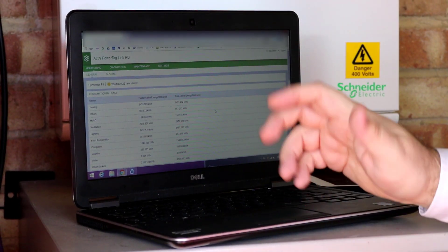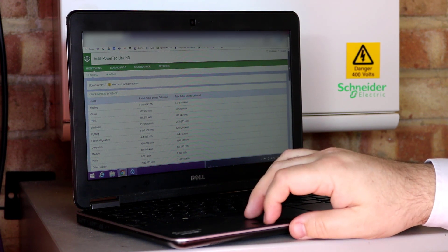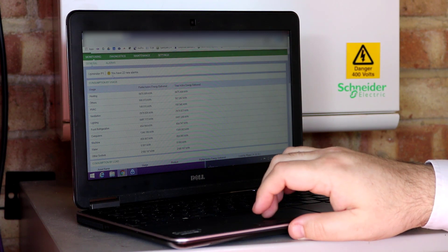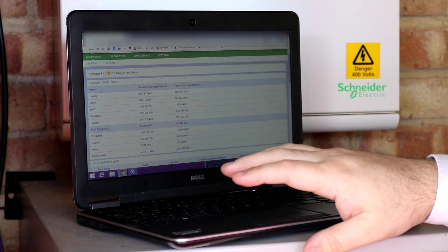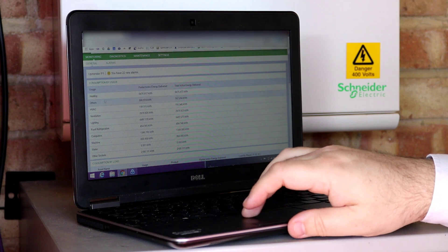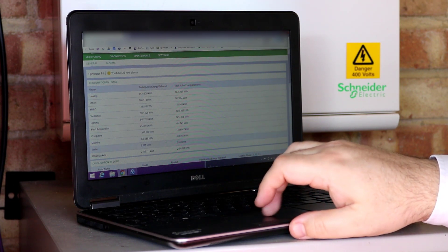I'm now dialling in via wireless connection to the Acti9 PowerTag board, which is based at Upminster on Platform 1. As you can see, we've broken it down by usage into subcategories. You can change that, you can play around with it — you can put it all under lighting, others, machines, HVAC, or heating. And what that does is show you real-time energy usage.